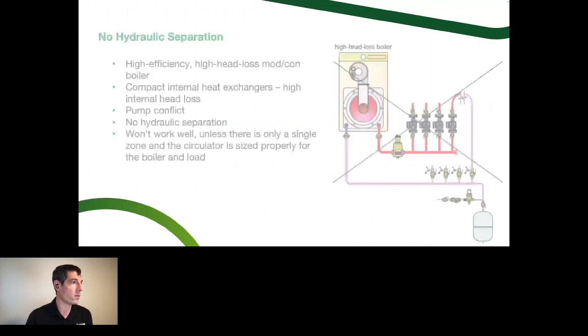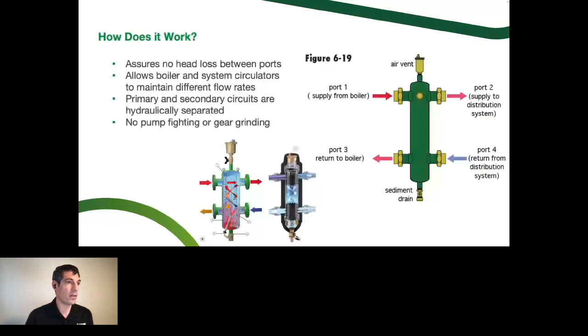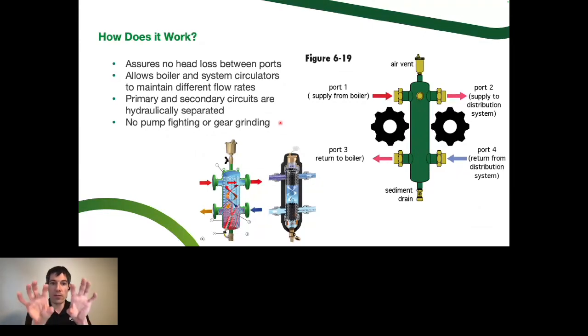So what do we do instead? Simply speaking, what we're doing with primary secondary piping is we're just separating these two wheels. So this machine, as Hart mentioned, is now, we've unbroken it. This is a functioning machine again because these gears aren't touching each other. So these gears can spin at different speeds and they're not grinding. They're not creating an issue where they would bind up or we're influencing flow on one side or the other. So that's kind of the essential piece of primary secondary piping.